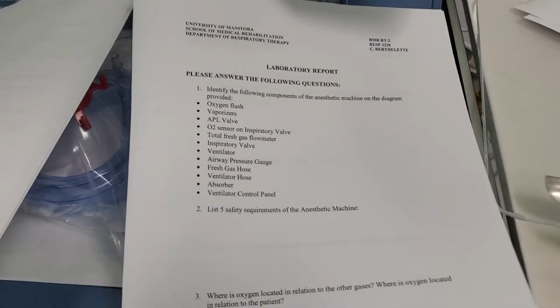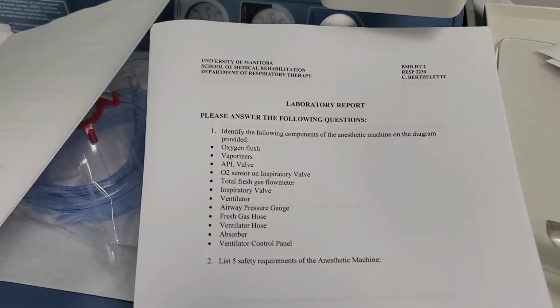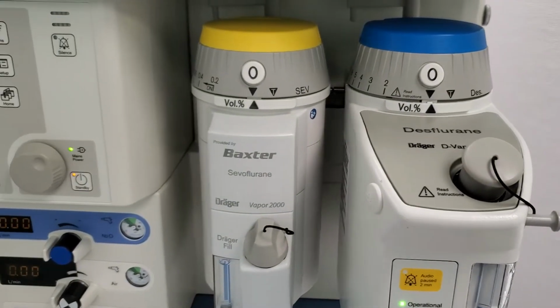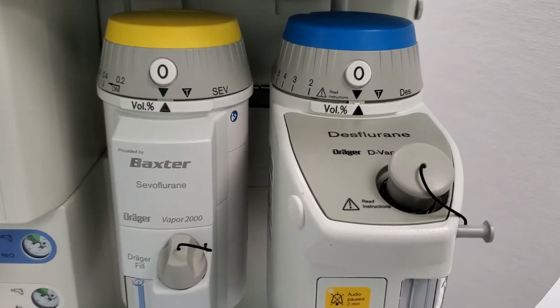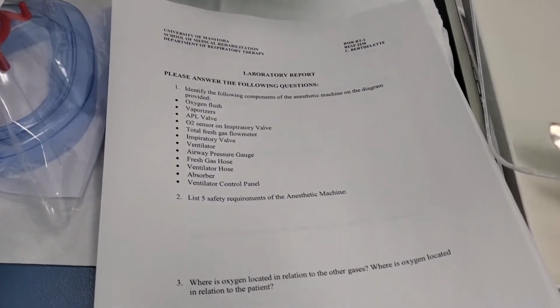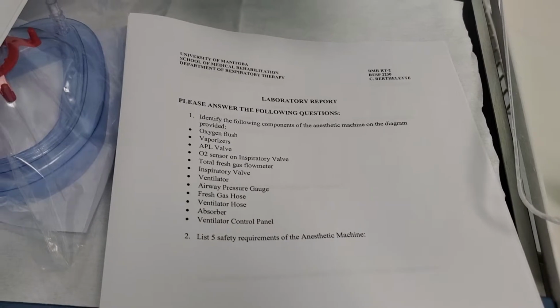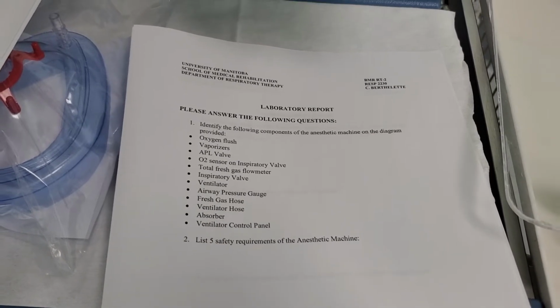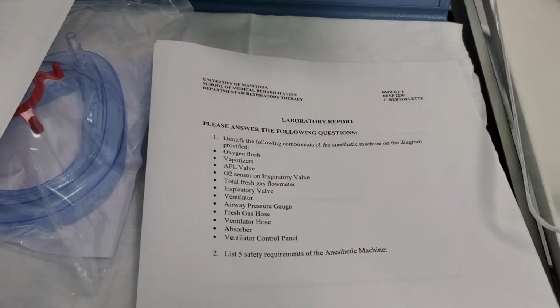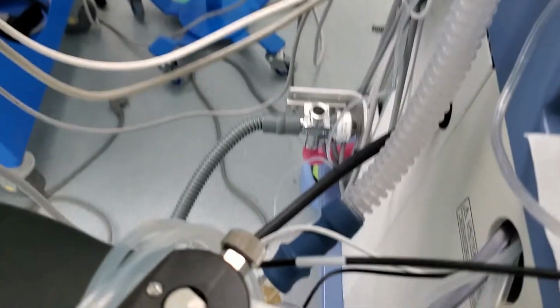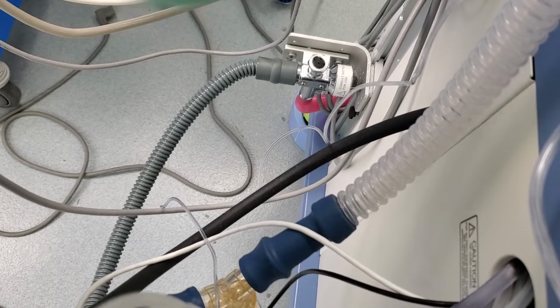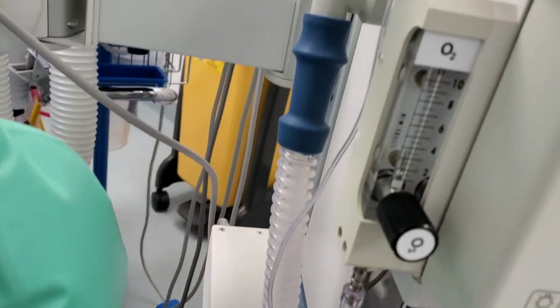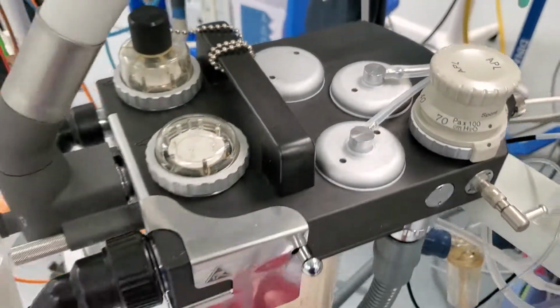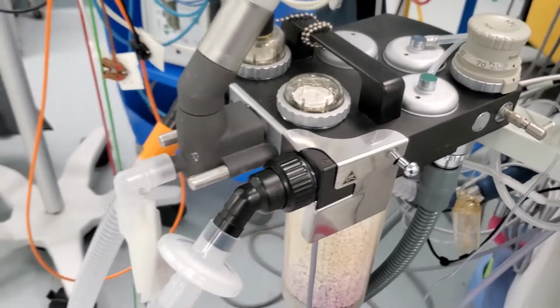So I've showed you a lot of the components, if there's anything that we're missing here. These are the vaporizers right here. This is our sevoflurane, this is our desflurane. We'll come back to those in a few minutes just to explain some safety features about those as well. I've showed you the ventilator, the airway pressure gauge, the fresh gas hose. This is this black hose here, so it'll be the black hose on the diagram, and then the clear hose is the ventilator hose. So it's coming from the piston to this block here that's called the COSY, and then it goes to the patient's circuit.